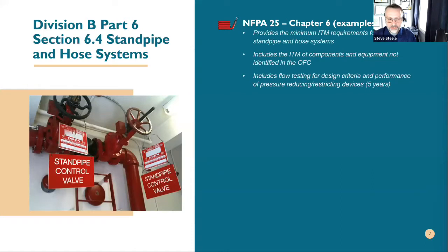So we have flow testing as well. I know there's some instances of flow testing. We'll get to those criteria in the OFC, but so full flow testing, design criteria, performance. So every 5 years, you're going to be testing or verifying the water availability for that full standpipe test. And then also the hydrostatic testing, and this one in particular we'll get into in the next slide, of dry system, anything that has dry system piping, so semi-automatic, full dry system. You get into some of the construction projects that are longer than 5 years, your temporary standpipe, all that has to be hydrostatically tested as per 25 every 5 years. That includes the FDC pipe.